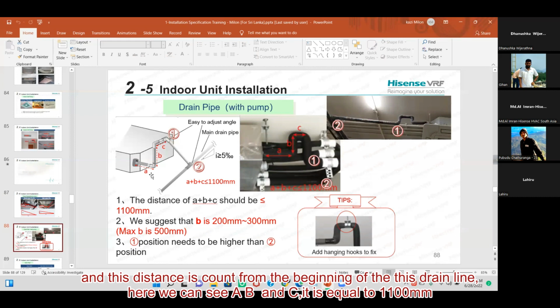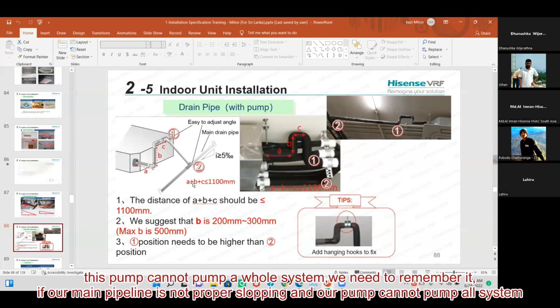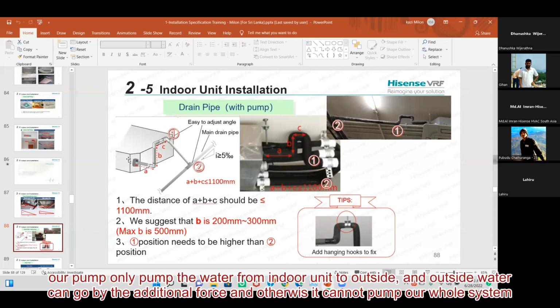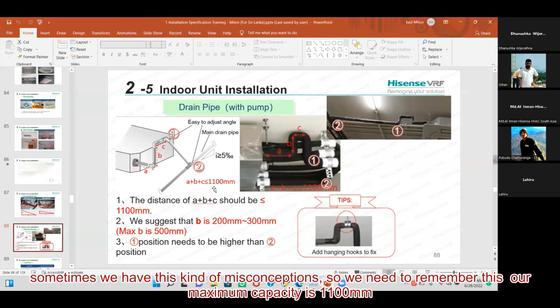Like here we can see A, B, and C, and the summation of A, B, and C is equal to 1100 millimeters. This pump cannot pump the whole system. If our main pipeline is not properly sloped, the pump cannot pump the whole system. The built-in pump only pumps the water from the indoor unit to outside, and outside the water can go by gravitational force. Sometimes we have this kind of misconception, so we need to remember this.